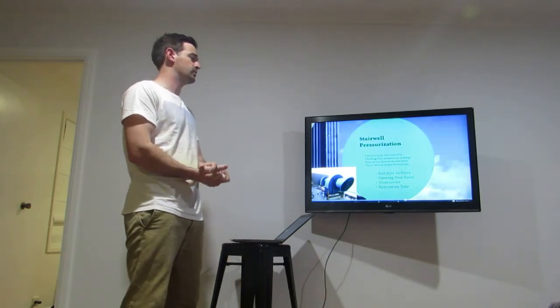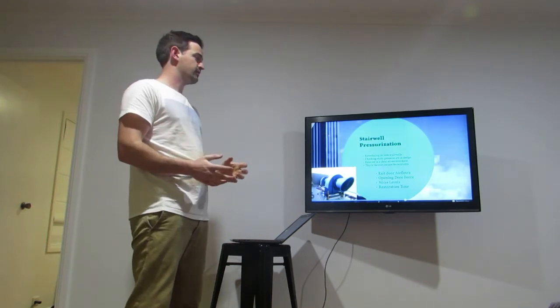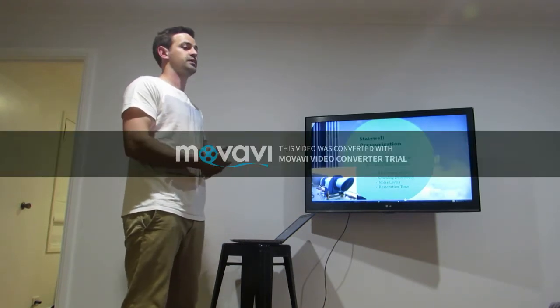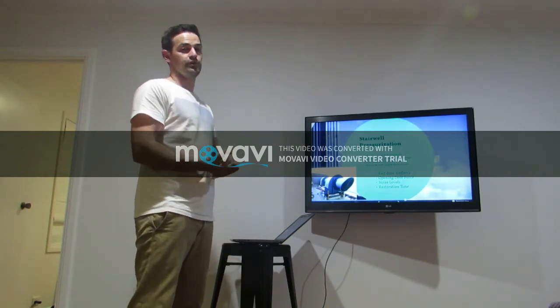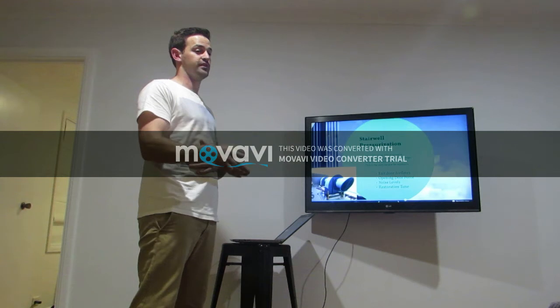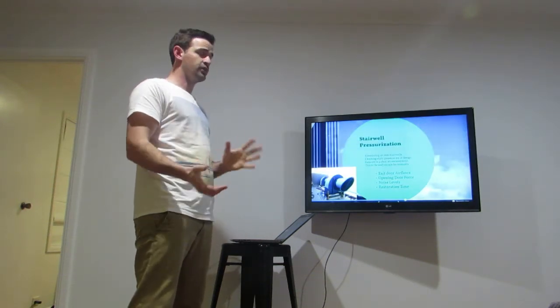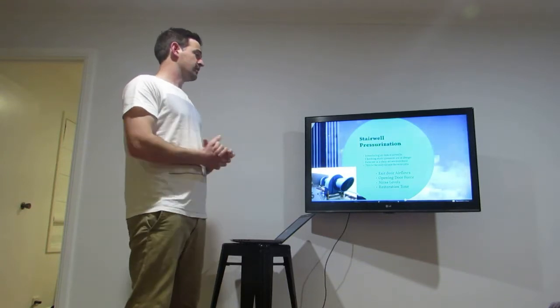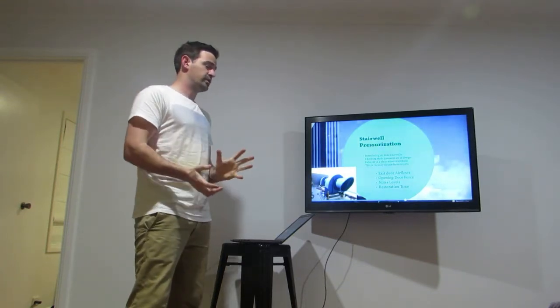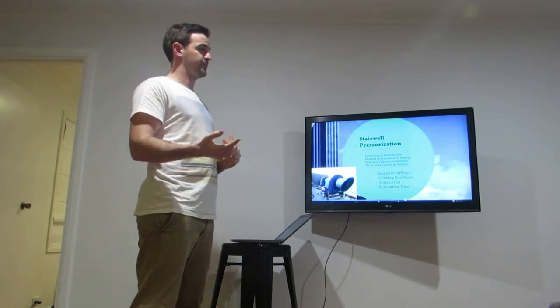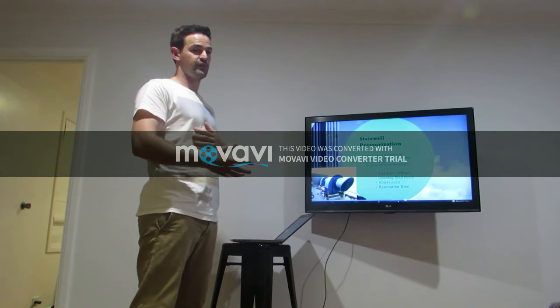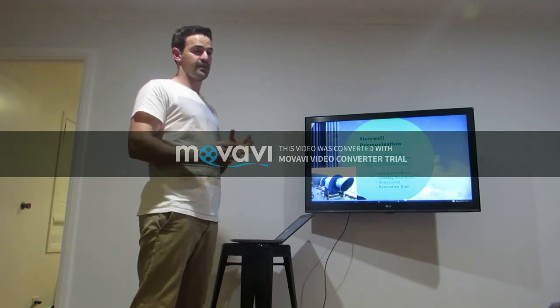Noise level is also really important. In a tenanted space, we don't want more than 65 decibels, and in the stairwells themselves, 85 decibels. People won't use a fire exit if it is too noisy, and noise is associated with a hazard. We also have restoration times for all of the checks. If more than 2 doors are open, we have a 10-second time frame that we check to make sure the fans react, ramp up, ramp down and get back to the specifications.